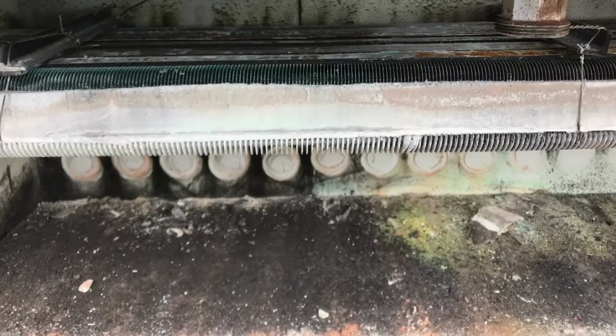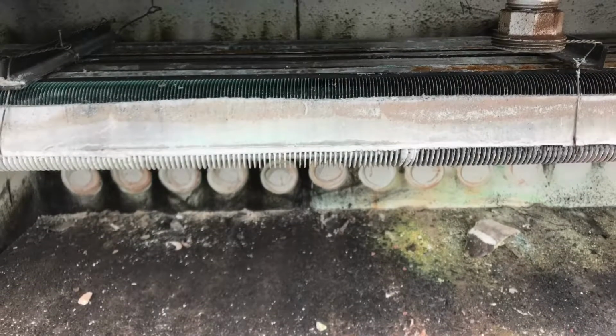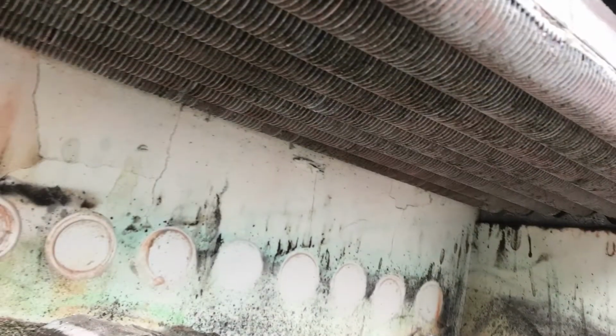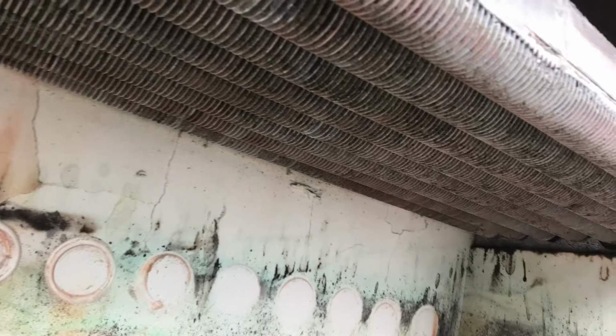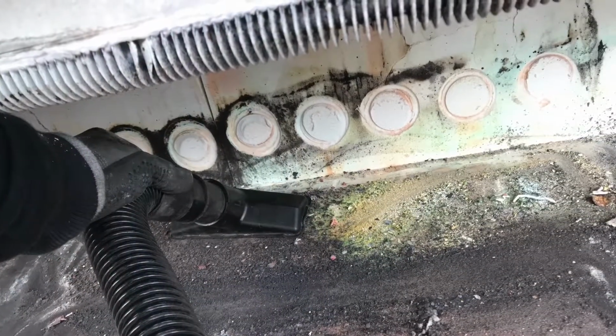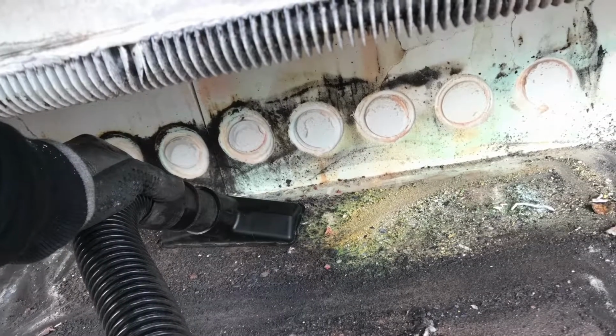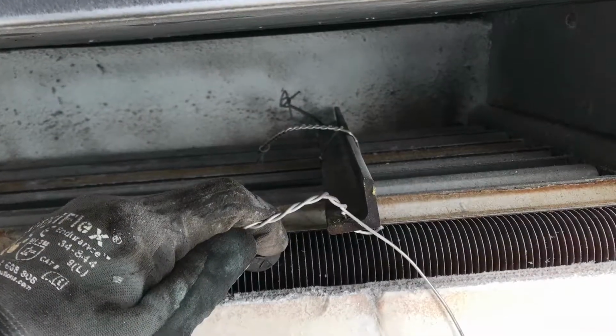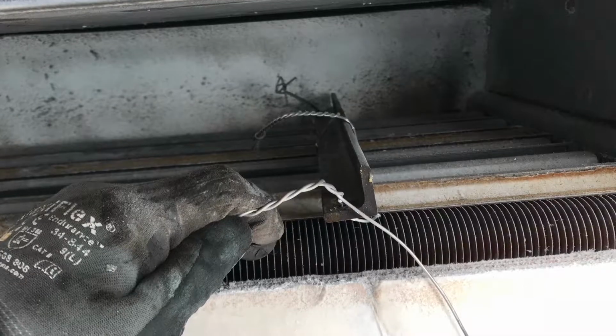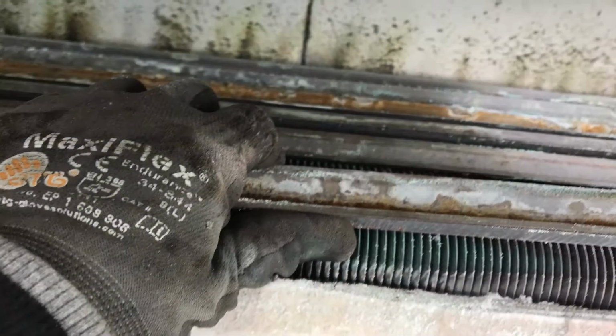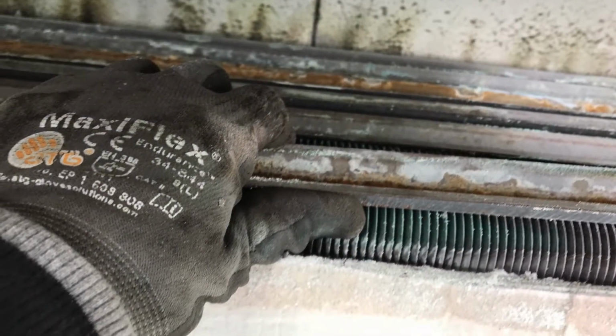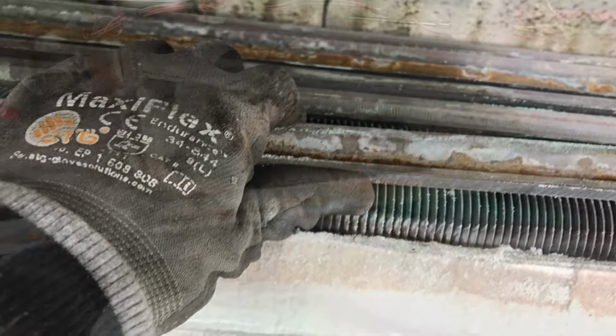This is the heat exchanger. Looks like it needs a good cleaning. A lot of calcium buildup and soot. So vacuum out all the debris. Take off the wires that are holding the angle that holds the plates on the top. Remove the angle plates, the diffusers.